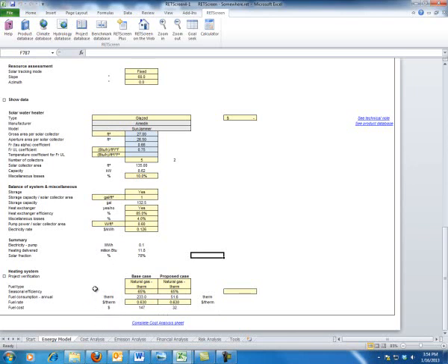All right, now look at this. Here's the difference. Let's take a look at how much energy I'm going to be saving throughout the year. I currently am going to utilize 233 therms. By putting the solar thermal system up, I am going to only use 51.6 therms. And at the cost of 63 cents per therm, which is a rather conservative number, but as of late, the last 3 years, our natural gas has come down, so I'm being conservative. What that means is I would have spent $147, and now $32 by putting this system up.